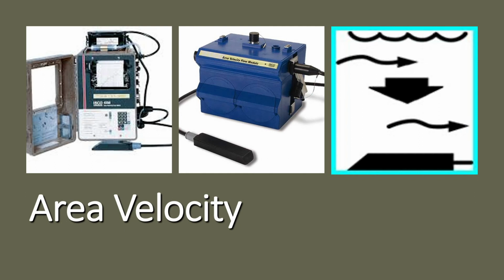Area velocity is another very popular flow measurement technique. This is a contact measurement technique in that an area velocity sensor both measures the level above the probe with a pressure transducer, and it also measures the velocity with an ultrasonic measurement device. That allows us to calculate the area, the velocity, and of course, Q, which equals A times V.